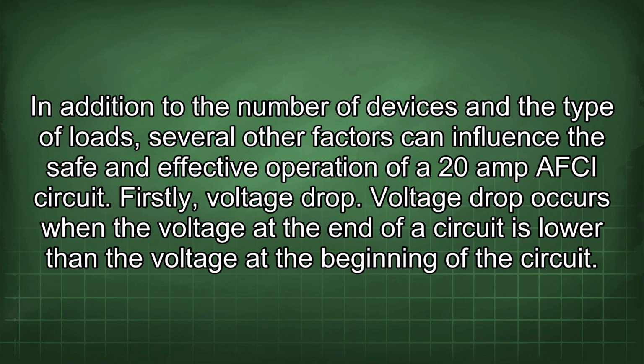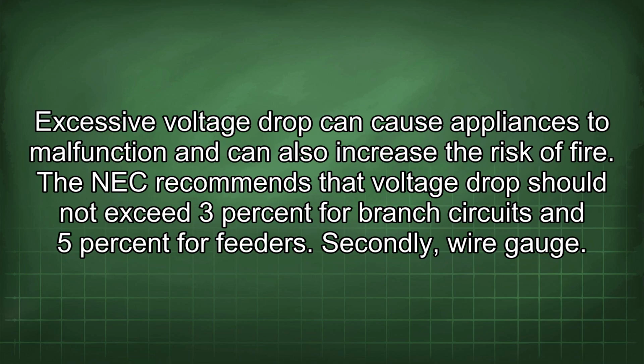Firstly, voltage drop. Voltage drop occurs when the voltage at the end of a circuit is lower than the voltage at the beginning of the circuit. Excessive voltage drop can cause appliances to malfunction and can also increase the risk of fire. The NEC recommends that voltage drop should not exceed 3% for branch circuits and 5% for feeders.